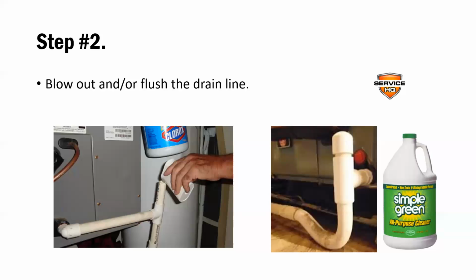So you can treat the line every so often with the Clorox or Simple Green. On this particular drain line right here, you would have to remove that cap that I've got my cursor on there. Remove the cap, dump some Simple Green down there, flush it out. That Simple Green does a great job of cleaning the algae and just cleaning the inside of that pipe out so we don't have any clogged pipes in the future.